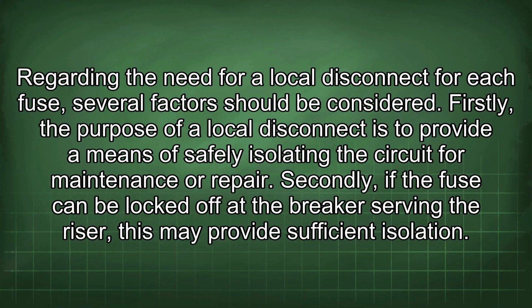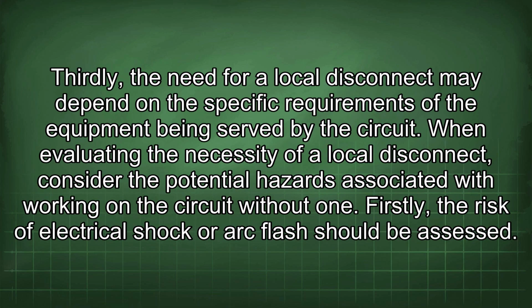Firstly, the purpose of a local disconnect is to provide a means of safely isolating the circuit for maintenance or repair. Secondly, if the fuse can be locked off at the breaker serving the riser, this may provide sufficient isolation. Thirdly, the need for a local disconnect may depend on the specific requirements of the equipment being served by the circuit. When evaluating the necessity of a local disconnect, consider the potential hazards associated with working on the circuit without one.